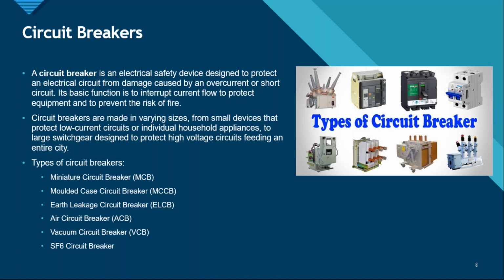Types of circuit breakers, like we discussed, they can be miniature circuit breaker, that's the MCB that we use almost every day. There can be molded case circuit breakers, that is the MCCB. There can be earth leakage circuit breaker, that is the ELCB. Right? There is a separate circuit breaker for earth leakage, in case there is high current flowing through the earth, that is also very hazardous. So there should be a circuit breaker connected to the earthing as well, or to the grounding as well.